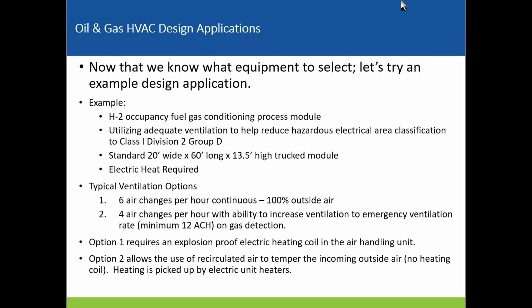So two typical ventilating options that we discussed to get adequate ventilation to reduce our hazardous electrical area classification would be to do 6 air changes per hour, like API RP 500 or 505 is pointing us to, with 100% outside air. Or you can look into the recirculating air option that Erik discussed, where we have gas detection and monitoring continuously, where we do 4 air changes per hour with the ability to increase ventilation to an emergency ventilation rate on gas detection.